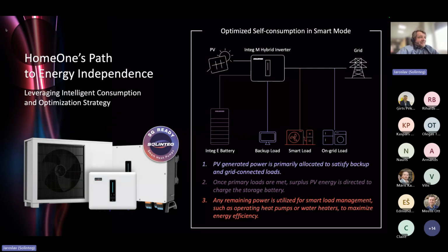Here you see again the optimizing of the smart control. We are also SG ready, and we are working with heat pumps which are SG ready. We can control them, and also other loads like a boiler, just through a digital output. The advantage is that you can set, for example, a scenario where, when the battery SOC is higher than 90%, you switch this dry contact on and switch on a boiler, and switch it off when the SOC value drops under 70%. This is very easy and many customers are using it.